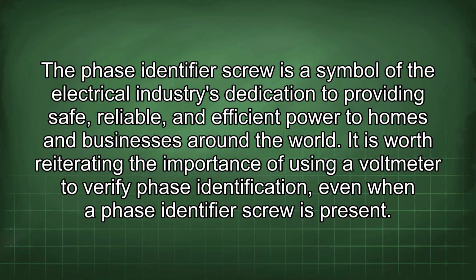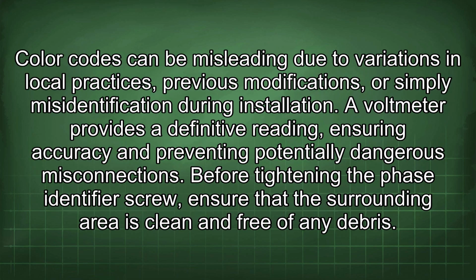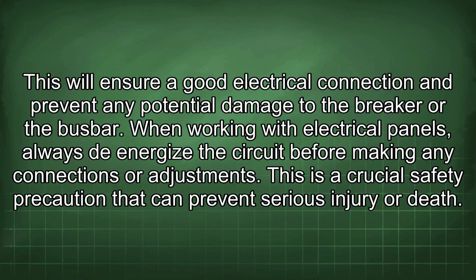It is worth reiterating the importance of using a voltmeter to verify phase identification, even when a phase identifier screw is present. Color codes can be misleading due to variations in local practices, previous modifications, or simply misidentification during installation. A voltmeter provides a definitive reading, ensuring accuracy and preventing potentially dangerous misconnections. Before tightening the phase identifier screw, ensure that the surrounding area is clean and free of any debris. This will ensure a good electrical connection and prevent any potential damage to the breaker or the bus bar.